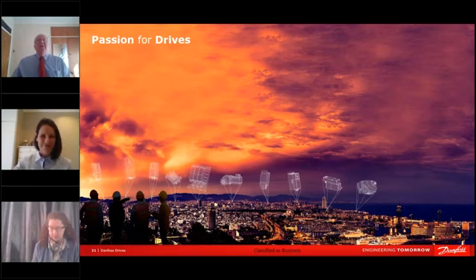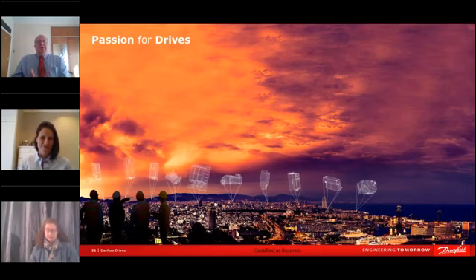Okay, the cost saving obviously would differ depending on whereabouts in the world you are, because the cost of electricity is dependent on its kilowatt hours, and these costs will vary. As you could see from the graph I presented earlier, with the fixed versus variable speed, if you're not running a motor at full speed, then there is a cost saving. And if you remember, we showed that with a 20% reduction in the speed, it showed a 50% reduction in the energy usage.